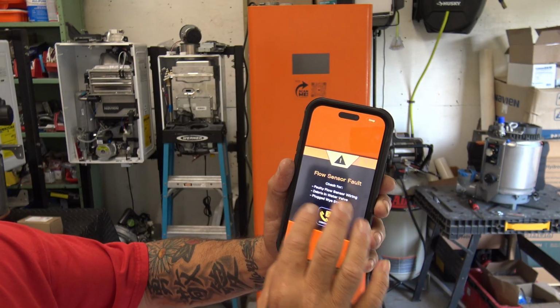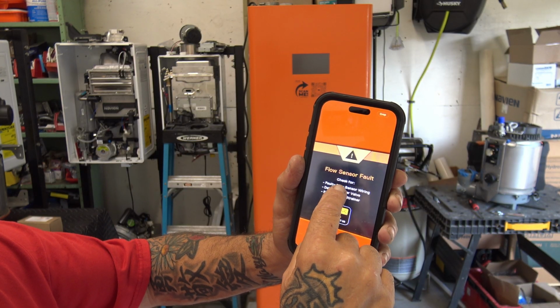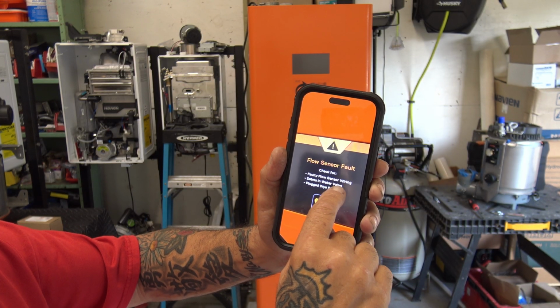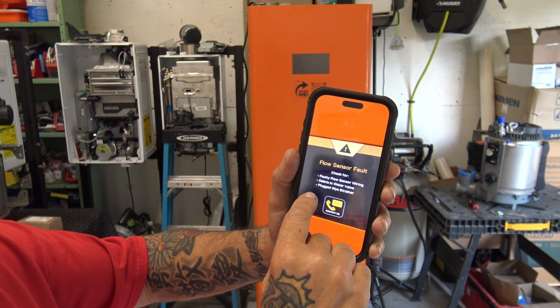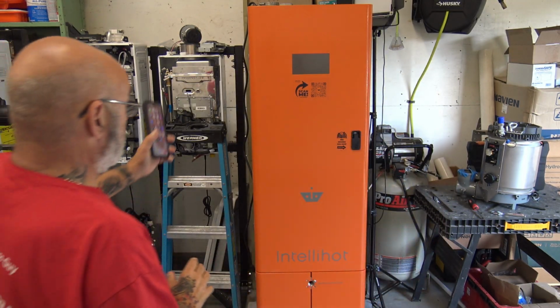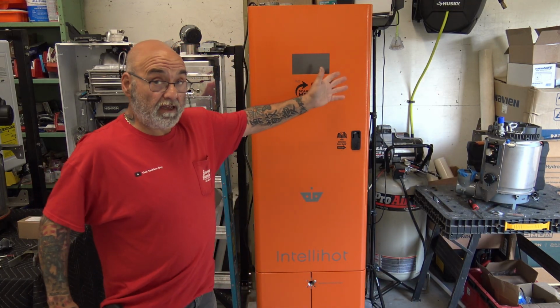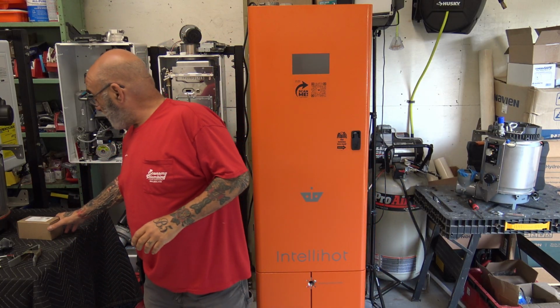They give you contact information and the fault: flow sensor wiring, debris in the valve, or a plugged Y strainer. Now on a 199, or the wall-hung units that only have one heat exchanger, it just says water flow sensor fault. So this is the part.